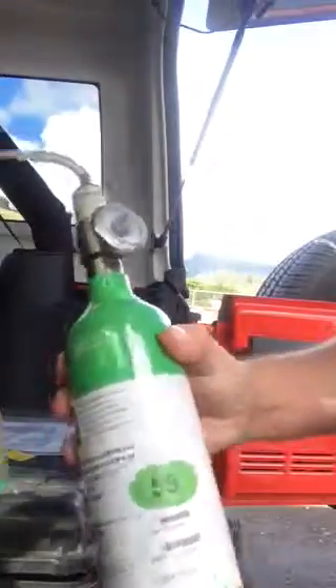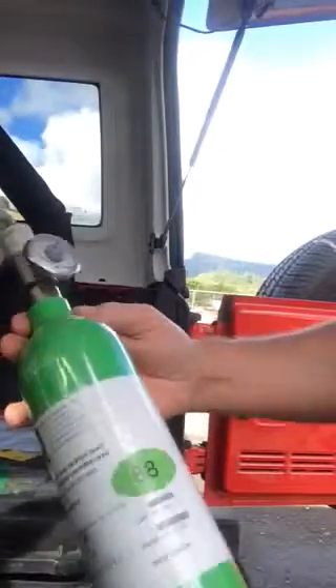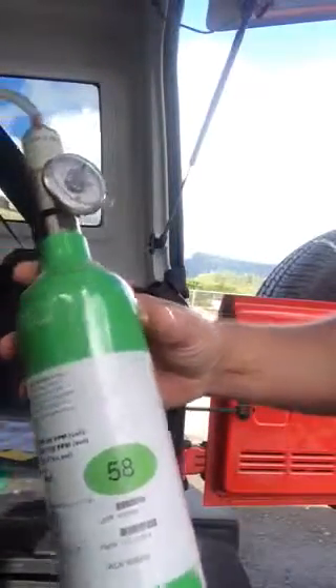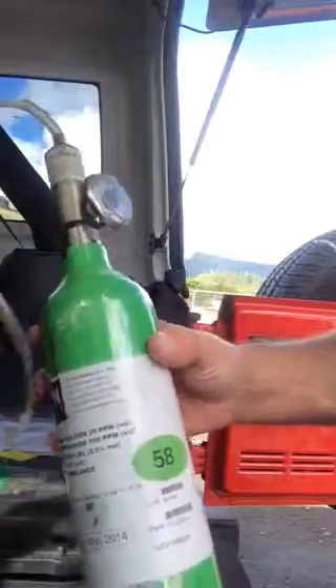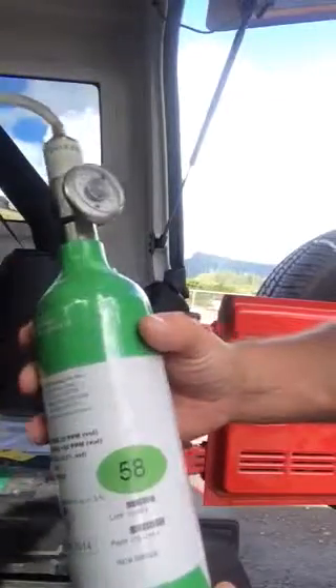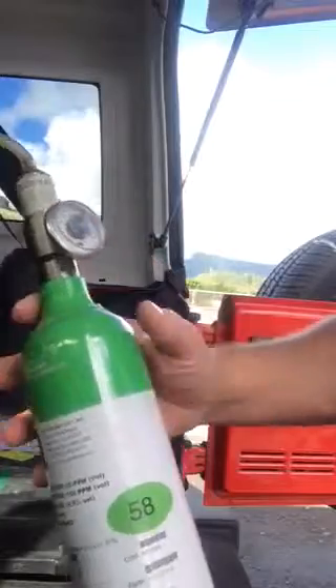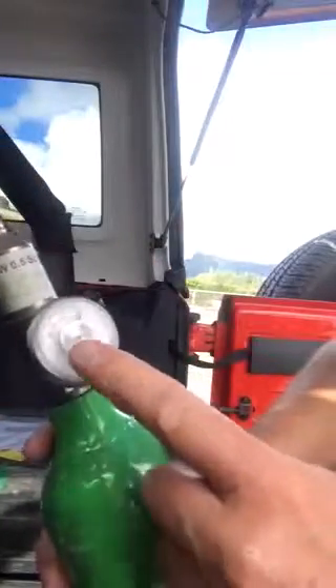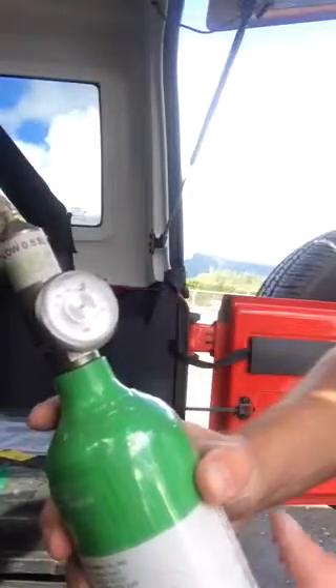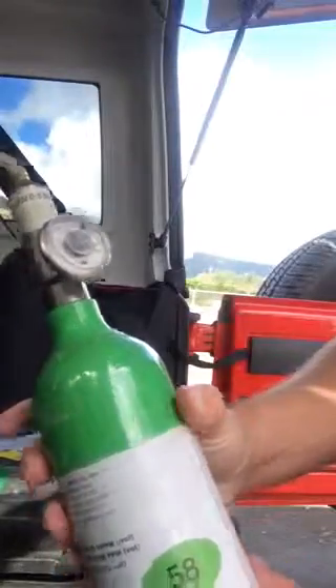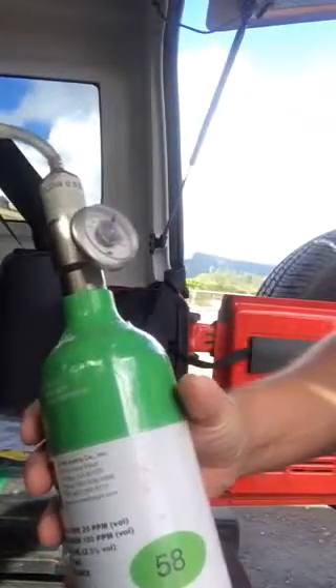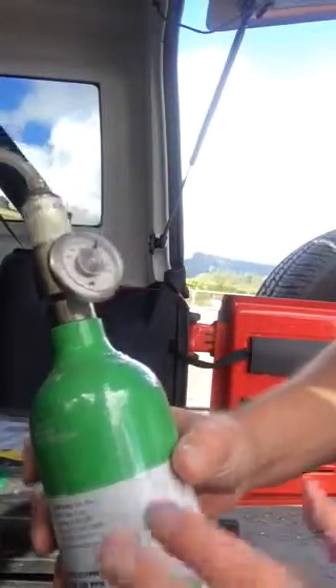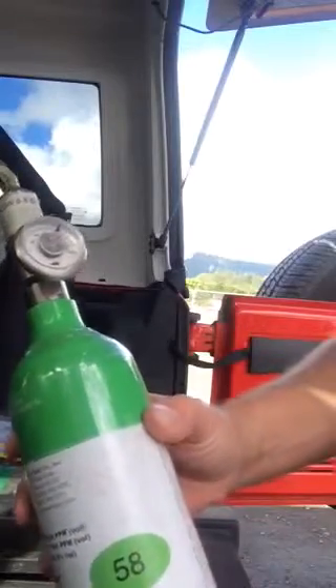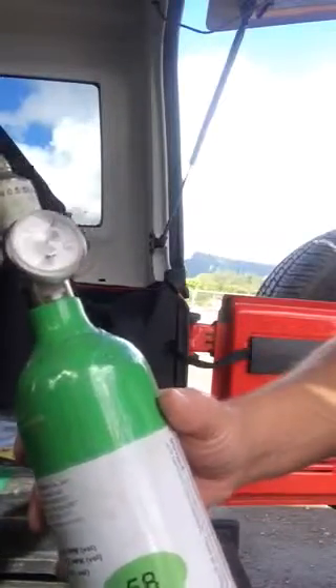And while that does its startup sequence, to do the calibration, you got to have the cal gas, just green bottle here. It's a mix of several different gases, different percentages that gets hooked up to it. When the dial starts to reach around the 200 range or below, it's time to replace the bottle. They become very inaccurate as far as doing the calibrations go, so you're not going to want to use that. So just let Tim know and he'll get one sent out to you.